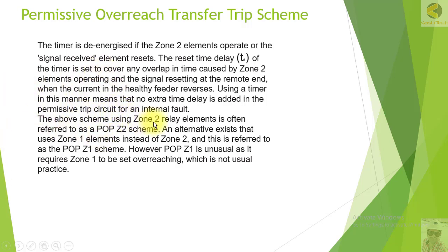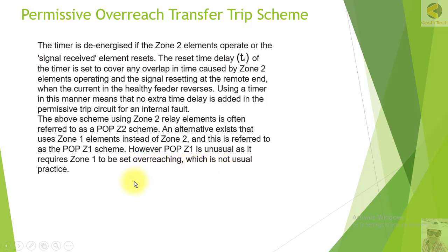The above scheme using the zone 2 relay element is often referred to as POP zone 2 scheme. An alternative uses the zone 1 element instead of zone 2 and is referred to as POP zone 1 scheme. However, POP zone 1 is unusual as it requires zone 1 to be set overreaching, which is not usual practice.